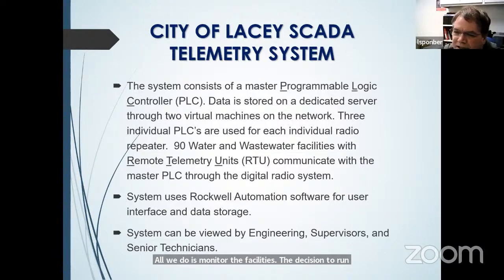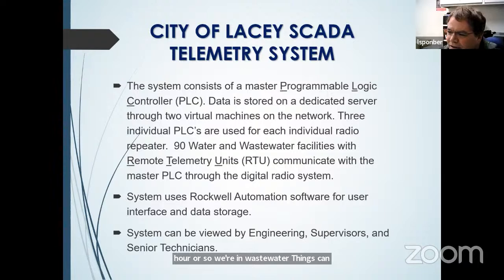The PLC is located at the facility. It looks at the liquid in the wet well, and then it determines to turn a pump on or not. Kind of, it's the criticalness of wastewater. You get the delay through the system to talk to that facility. And for instance, in an outage in water, sometimes a communication will quit, and it's not as critical that we talk to that, you know, every half an hour or so. Where in wastewater, things can get ugly pretty fast. So you wouldn't want that delay. So the decision is made at the site, and then it's monitored through the Scada system to determine if it's an alarm or not.